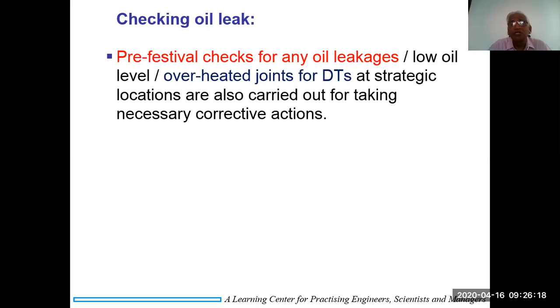specifying maximum flux density, standardized only for one particular capacity, maybe 315 kVA, total cost of ownership. Loss capitalization on total owning cost is carried out during the evaluation for procurement and selection. However, other factors like performance record of a vendor, after sales service, financial standing, concern for customer are also given due consideration. Pre-festival checks for any oil leakages, low oil level, overheated joints, and DTs at the strategic locations are also carried out for taking necessary corrective actions.